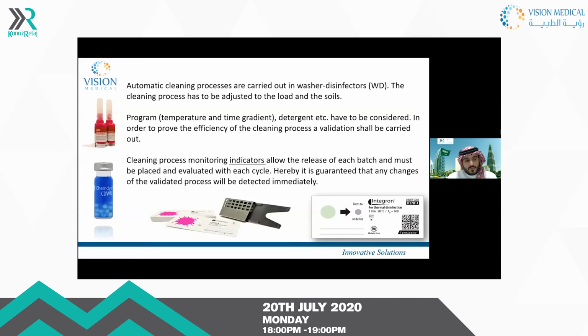Most washer disinfectors globally are open systems, so you can use any chemical and make a calibration. You can also have advanced indicators or advanced technology to make sure, during high-level disinfection or thermal disinfection inside your washer disinfector, that you are using the proper indicator. You can use it internally inside the washer disinfector to make sure it returns to the right color, reaching the level of disinfection.